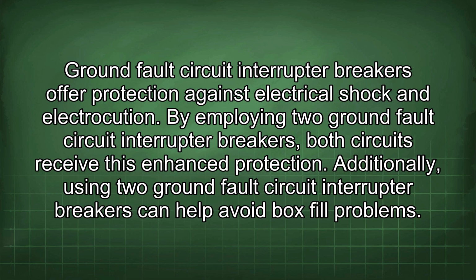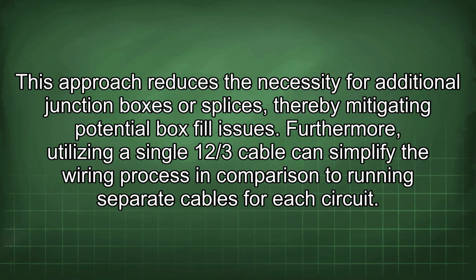Additionally, using two ground fault circuit interrupter breakers can help avoid box fill problems. This approach reduces the necessity for additional junction boxes or splices, thereby mitigating potential box fill issues. Furthermore, utilizing a single 12/3 cable can simplify the wiring process in comparison to running separate cables for each circuit.